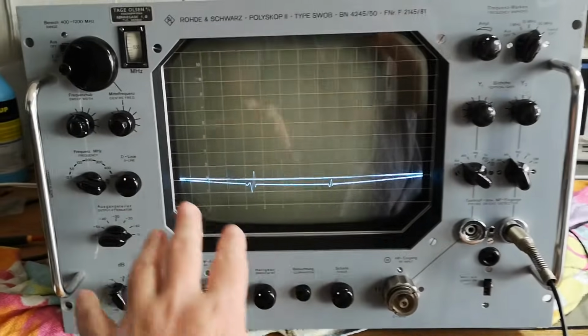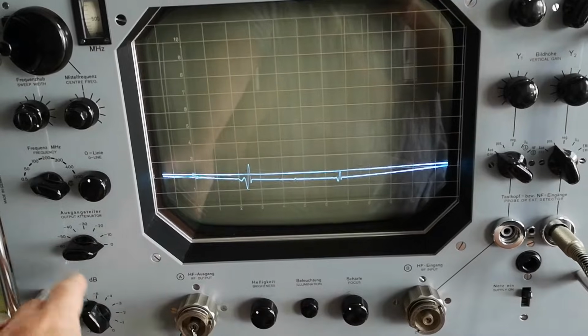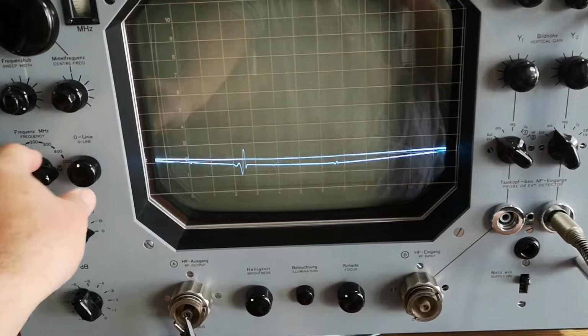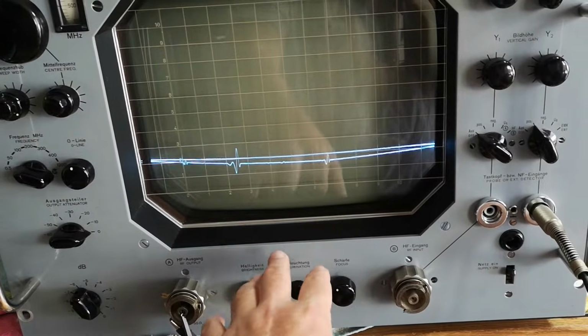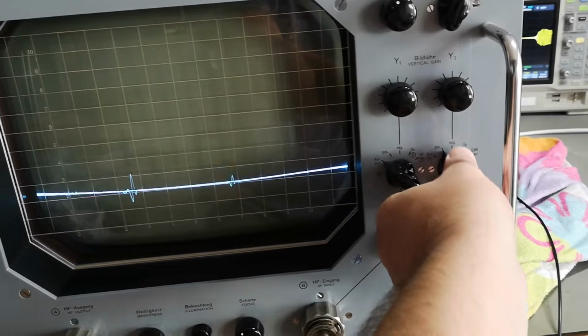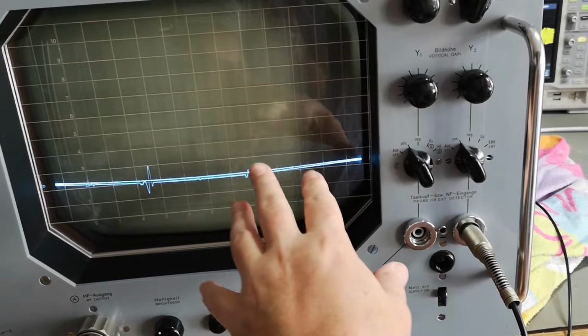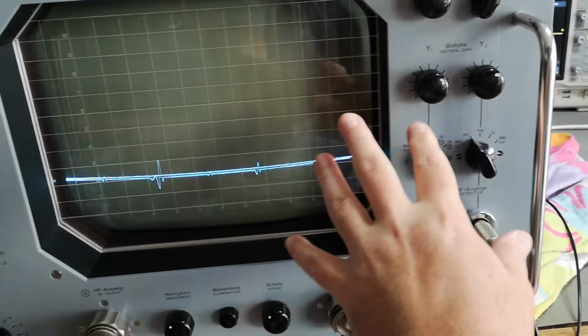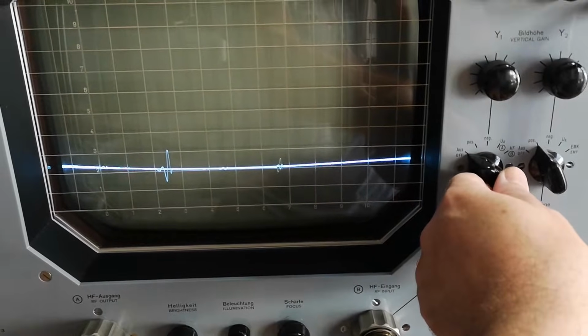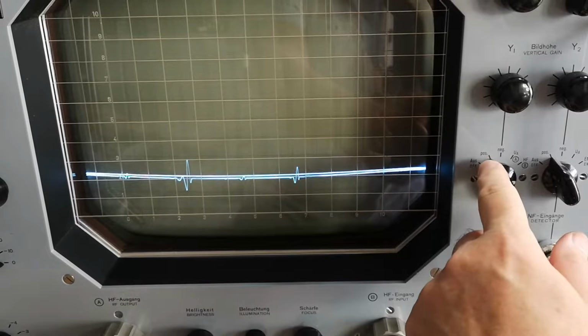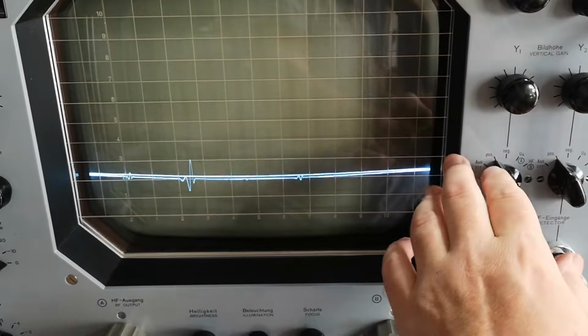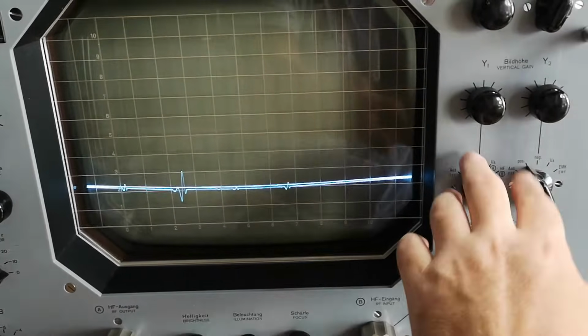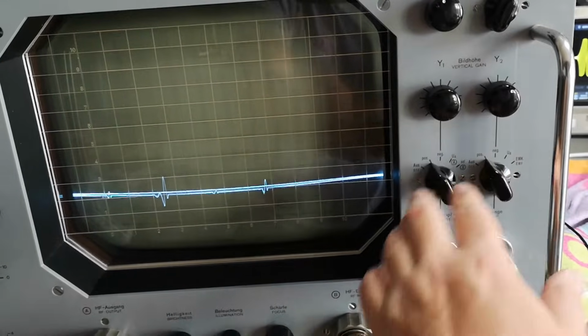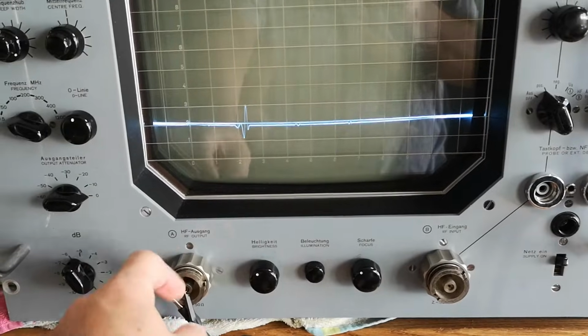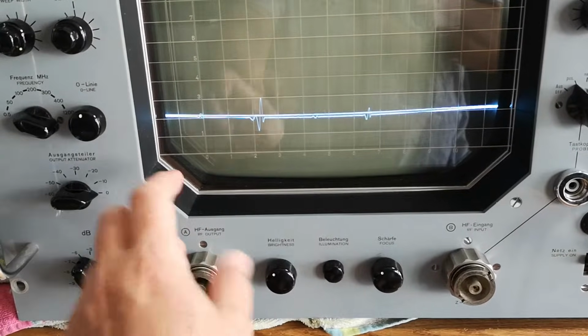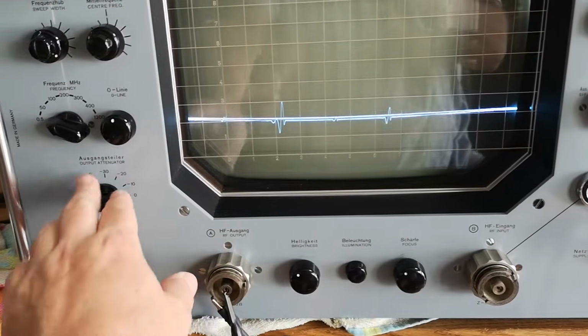So I've been doing a lot more tests on this unit. I've been playing around with all the different inputs and settings, and I think it's actually working. See, if I turn on the different channels, it is in alternating mode, the two different inputs. I don't know if you can see, it's now not blinking so much, but if I turn the other channel on here, it's now blinking. So that is how it is, alternating between the two input channels, so it doesn't measure exactly at the same time. But it doesn't matter, since the output signal, the stimulus for your measurement, is just coming every time. So that is not a real problem in this case.